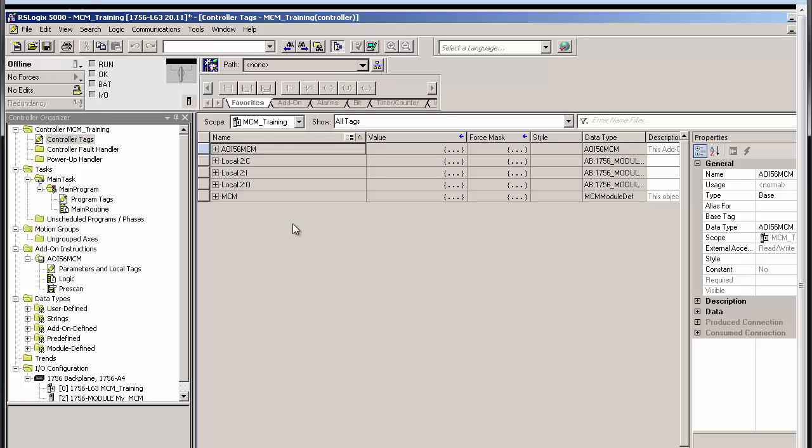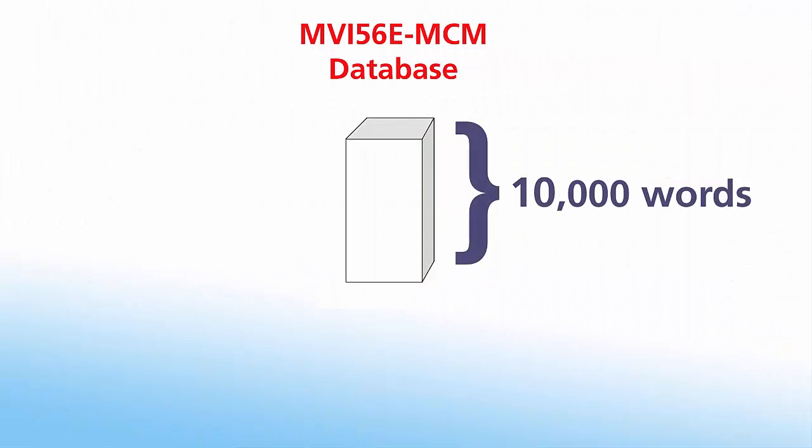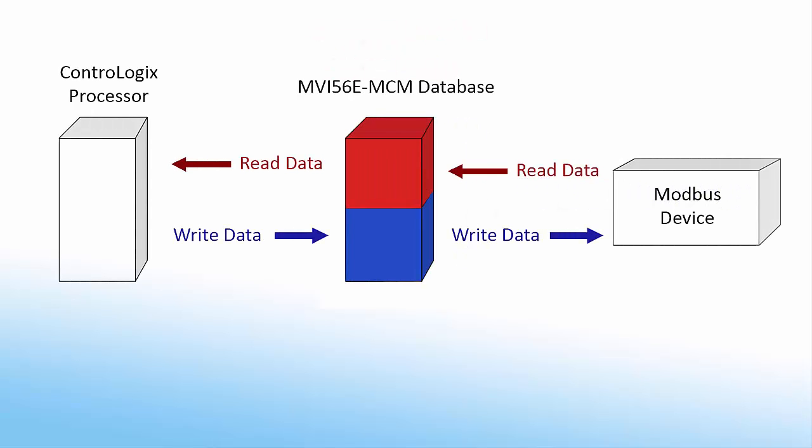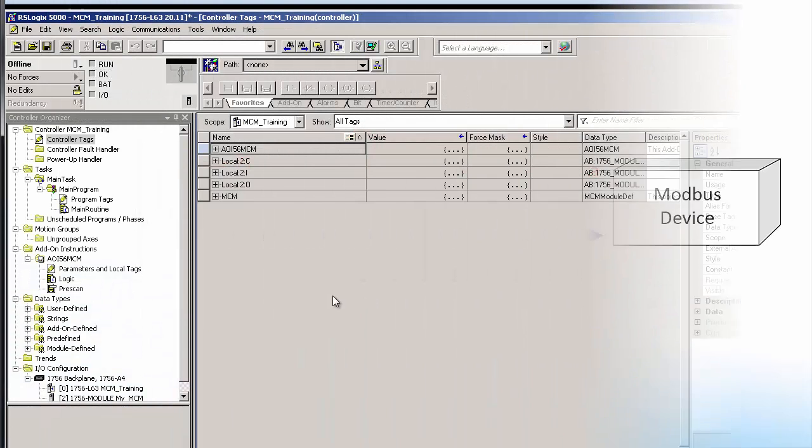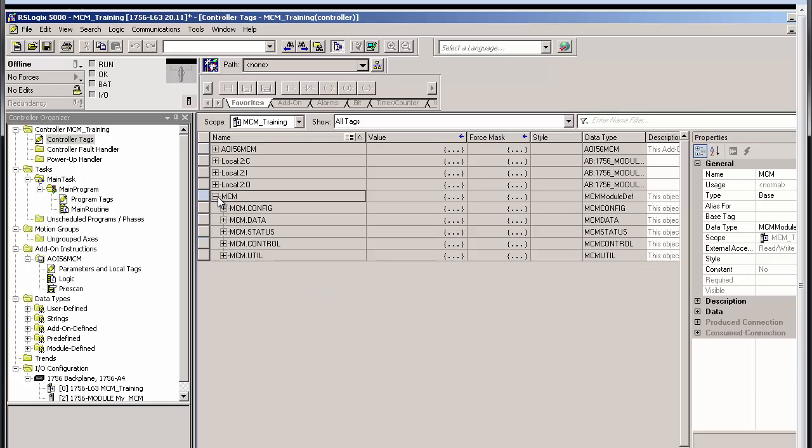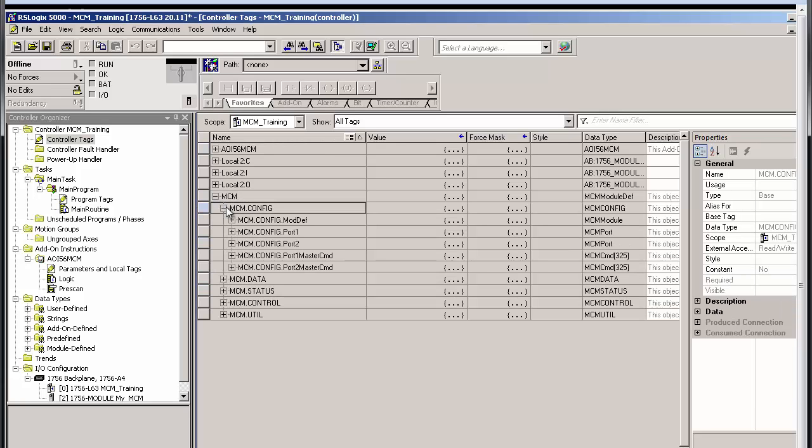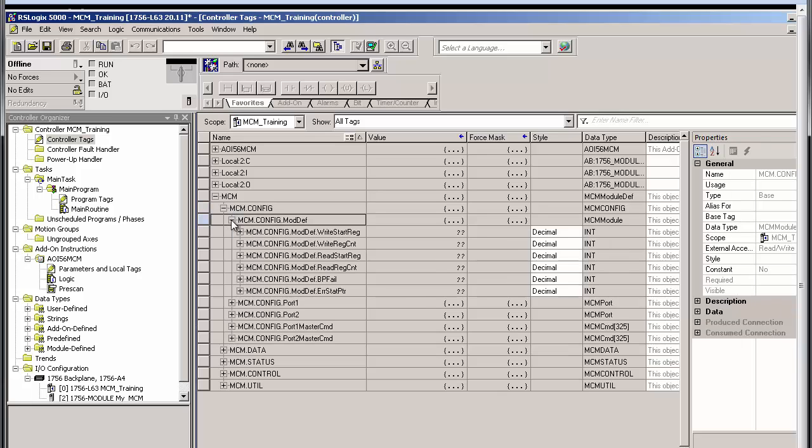The MVI56E MCM module has a database of 10,000 registers. Typically, you can think of this database as having two sections, read data and write data. The read data is sent to the ControlLogix CPU from the network, while the write data is read from the ControlLogix CPU and then sent out over the network. To configure the MCM's database, we'll use the MCM.config.moddef controller tag. The moddef tag configures the entire module's database. I'll go through the essential entries here.